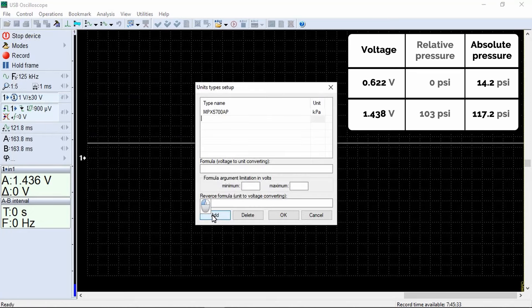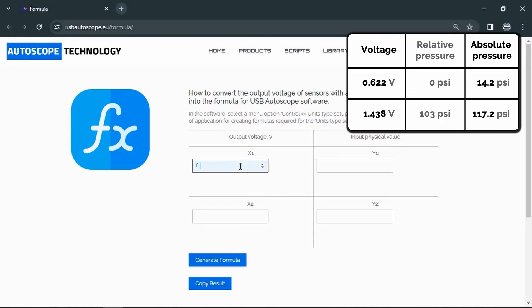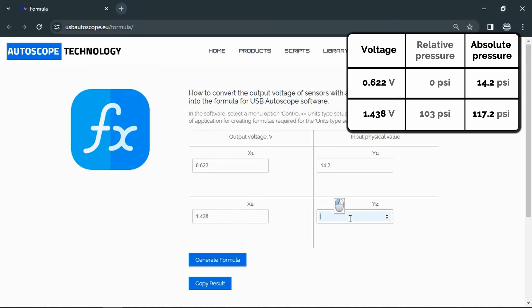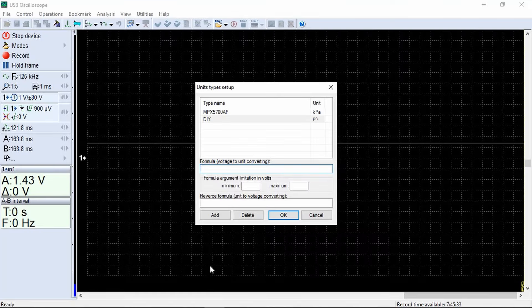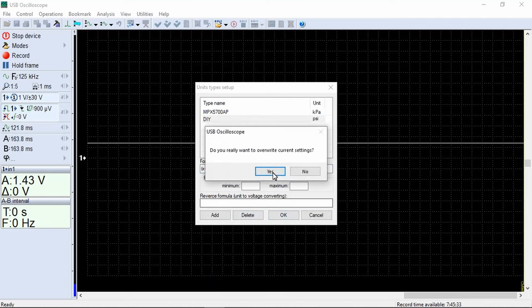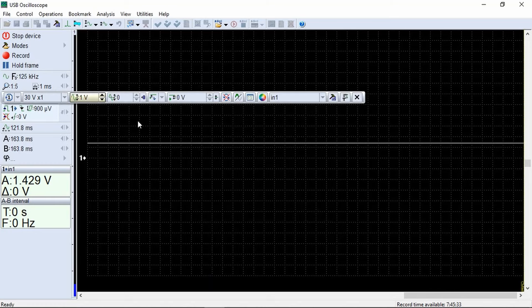We will name this transducer DIY. The unit of measurement will be PSI. A voltage of 622 millivolts corresponds to an absolute pressure of 14.2 PSI. A voltage of 1.438 volts corresponds to an absolute pressure of 117.2 PSI. We insert the generated formula, press OK, and confirm the changes. Support for the new pressure transducer has been added to the program.